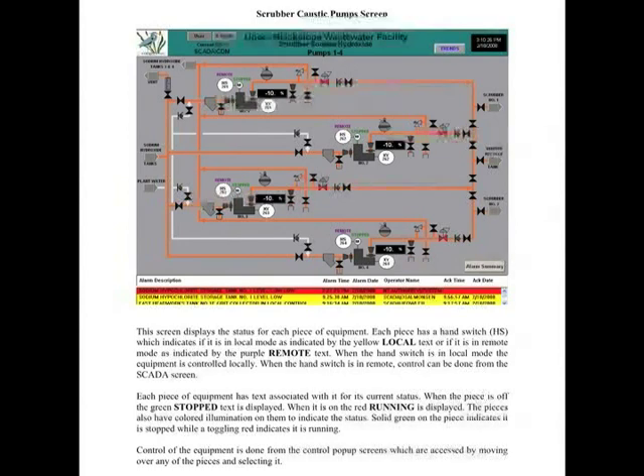In manual mode, depending on how you valve this, if you just change around some of the valving, you can have pump 4 feed scrubber 1. But it only can happen in the manual mode. You won't have automatic control. You'll have to give it a set point for manual mode. Okay, any questions on that? It's a little confusing.